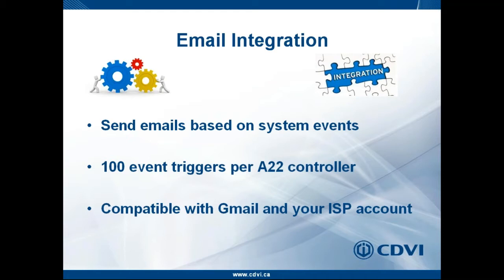You can have up to 100 different triggers per controller. In a system with several controllers each having expanders, each controller connected to the network can be set to send an email, and each one can have up to 100 different events as a trigger. When something happens on a controller or its expanders, it will send an email. This is compatible with Gmail, Yahoo, Windows Live, or your local ISP email account using SMTP settings and ports.